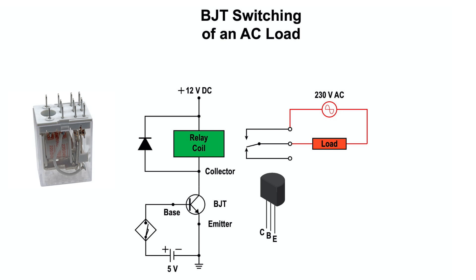When the proximity sensor switch closes, it establishes a small base current that drives the collector fully on to the point where it is said to be saturated, as it can't pass any more current. The relay coil is energized, and its normally open contacts close to switch on the load. When the transistor is in the on state, the collector current is at its maximum value, and the voltage across the collector and emitter drops to near zero, while the relay coil increases to approximately 12 volts.